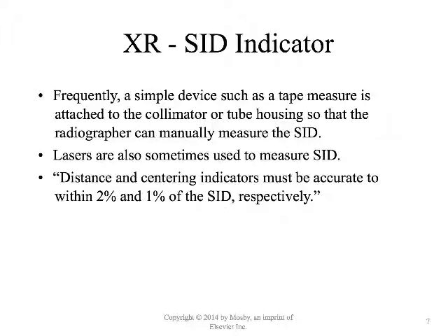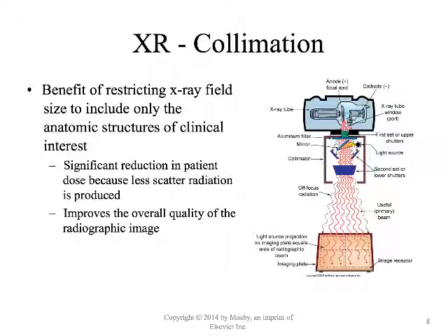The number that I would remember is 2% of those two. If you remember 2%, you're good to go. Are there questions about what I'm saying about that? Basically, what I'm saying is if it's not aligning appropriately, if there's not coincidence between the X-ray exposure area and what the collimator light shows you, it can't be off by more than 2%.